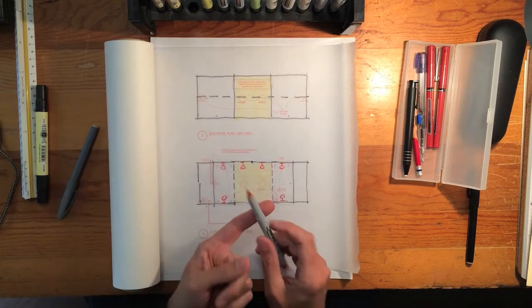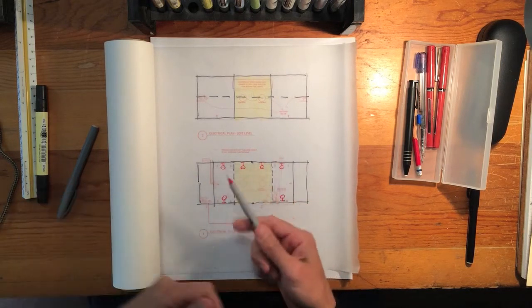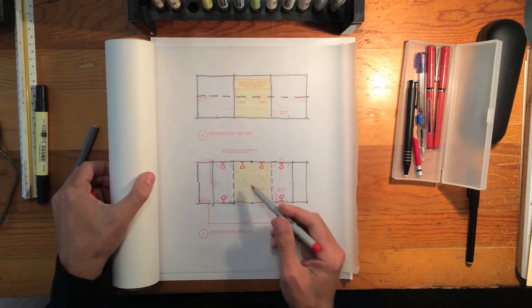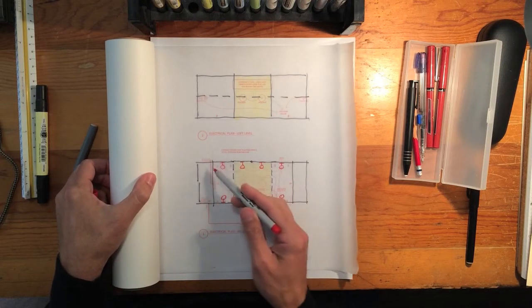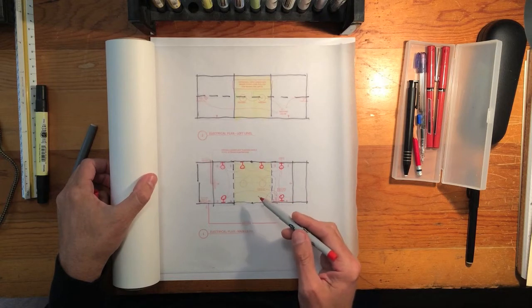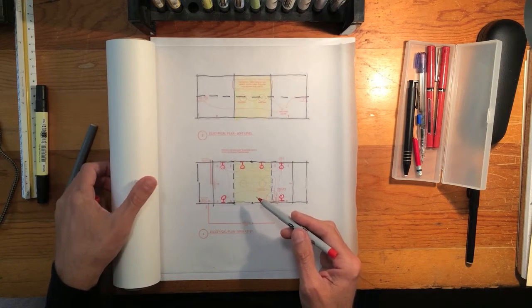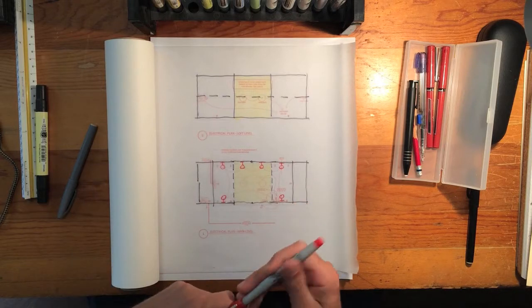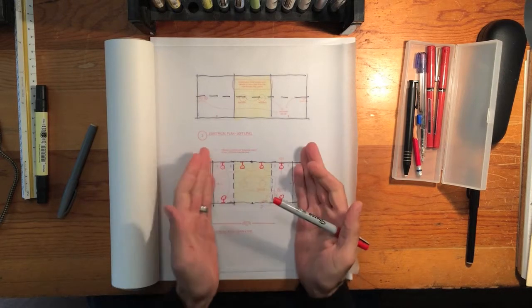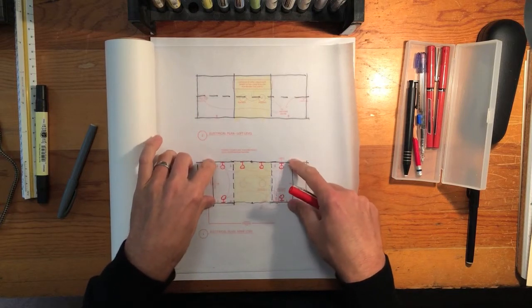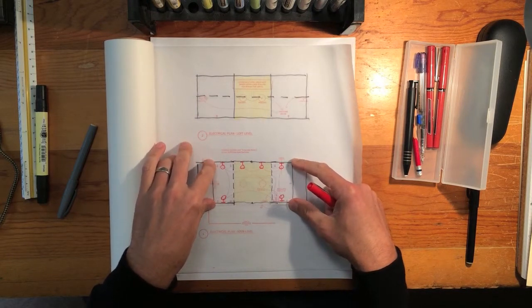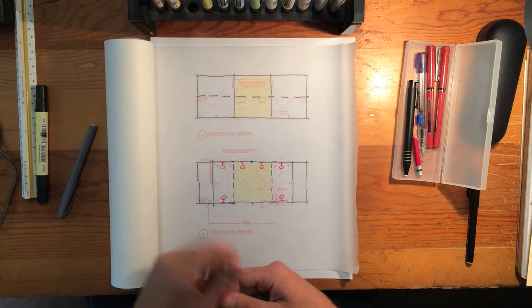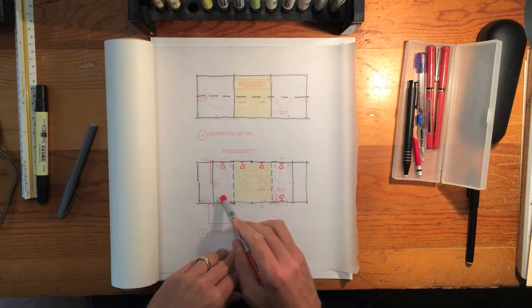As a general guideline, if you don't know how much light to put into a space, you can take the area, the floor area of the space you're trying to light, and multiply that by 1.5 to get just a general wattage for your fixtures. This particular space, this center space, is about 300 square feet, so if we multiply that by 1.5, we end up with 450 watts of fixtures.